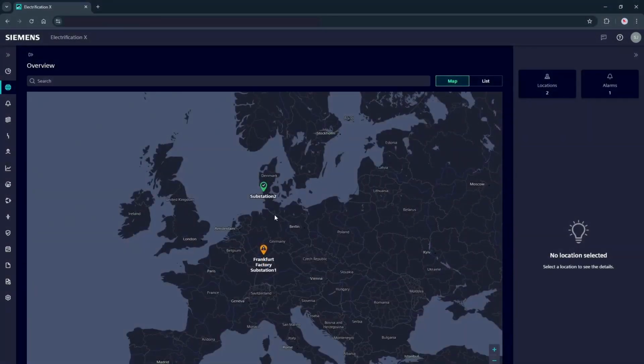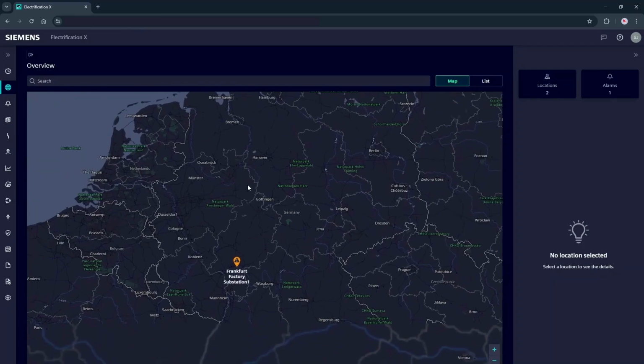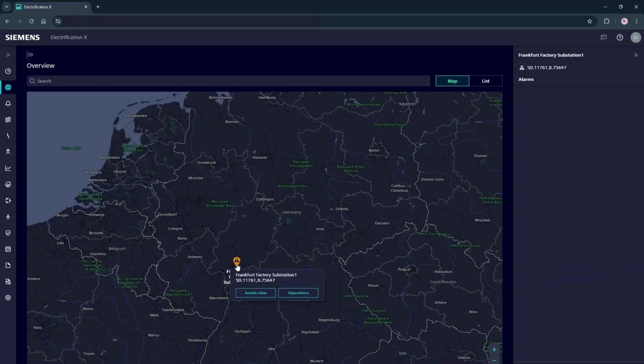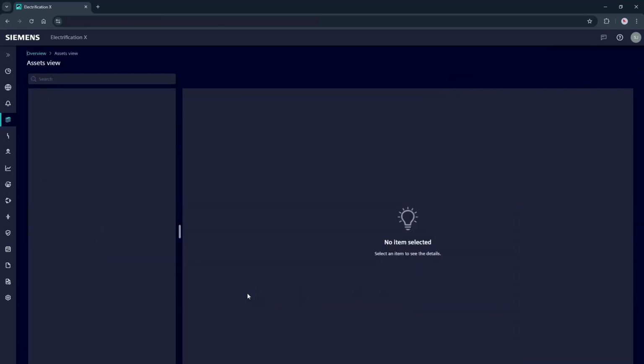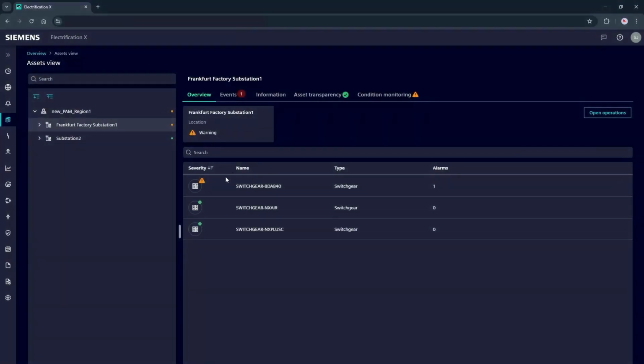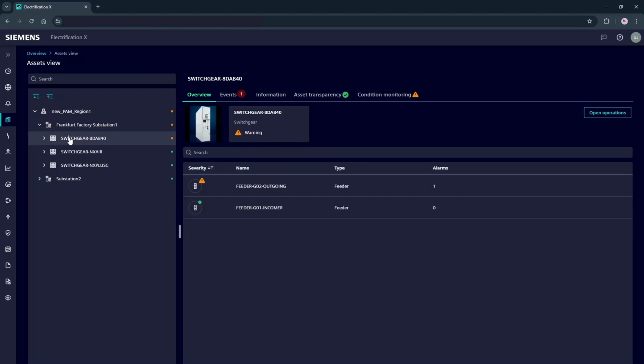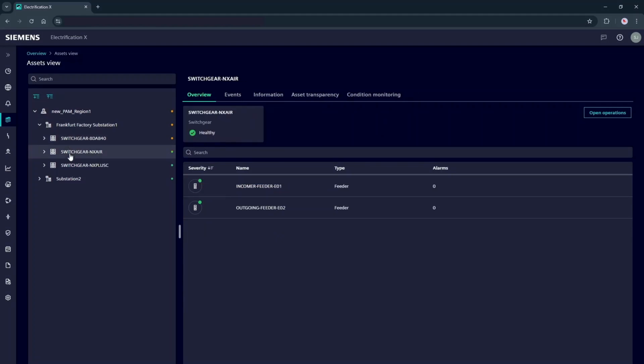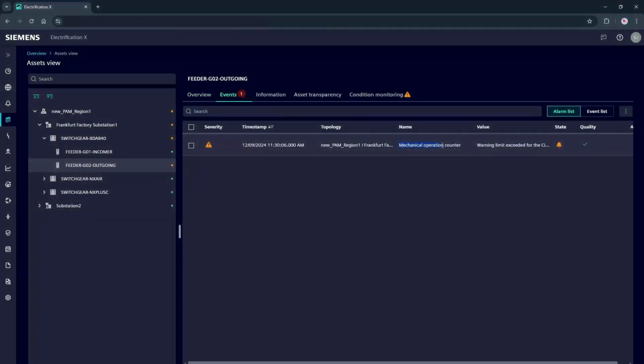Here, we see that an issue has been detected in Germany, at Frankfurt Factory Substation 1. Upon closer examination, we notice that the alarm was triggered from switchgear 8DAB40, associated with its outgoing feeder G02. The alarm signals a warning that the circuit breaker's mechanical operations counter limit has been surpassed.